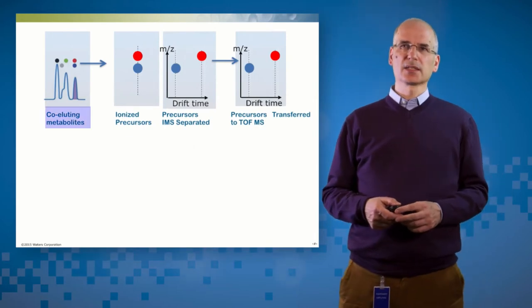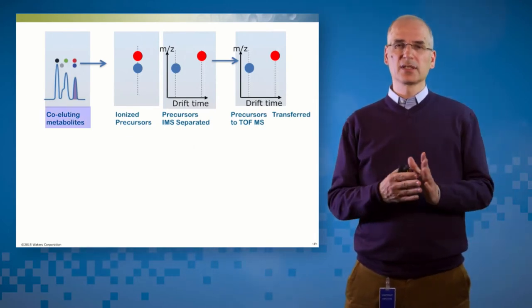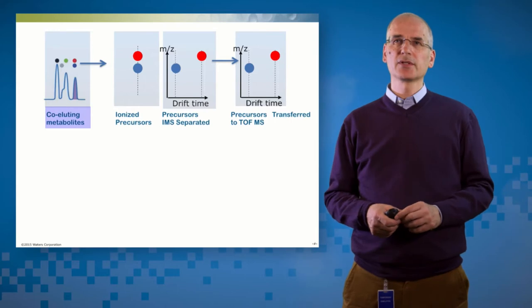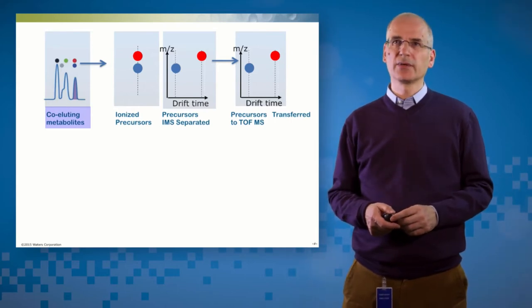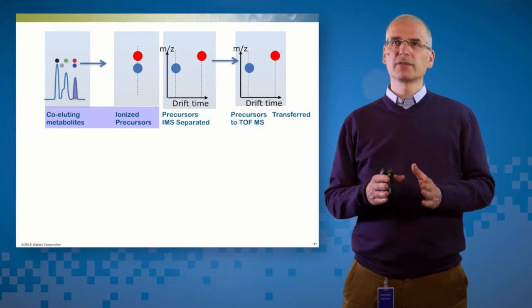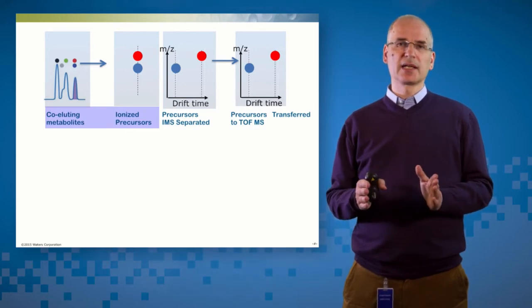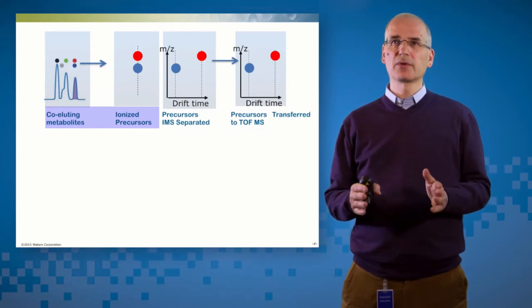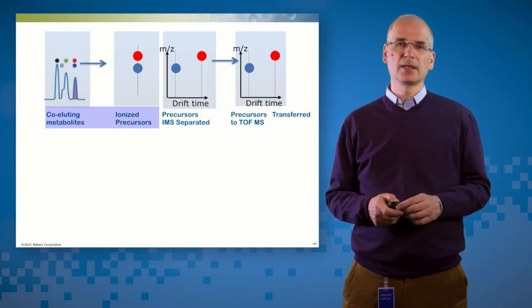So HDMSE works like this. We have metabolites separated by chromatography, but suppose that we have two co-eluting metabolites going into the system. They're ionized in the source, but in the middle of the instrument, we have an ion mobility cell. And in that ion mobility cell, we can separate the components based on their drift time, which is a function of their size and shape.